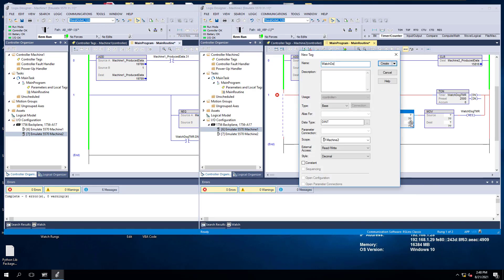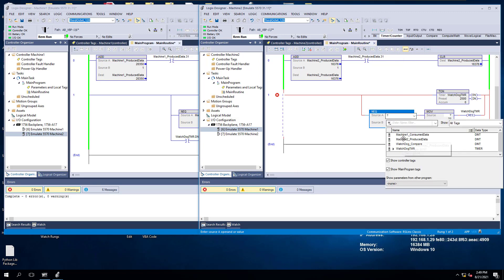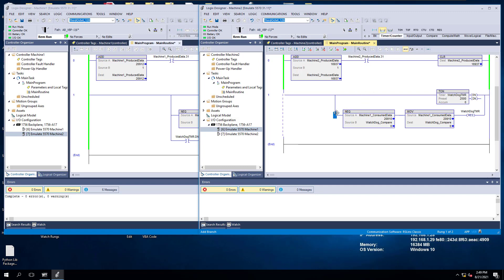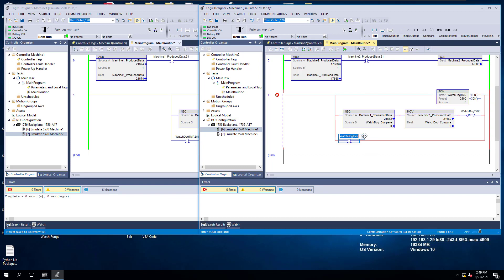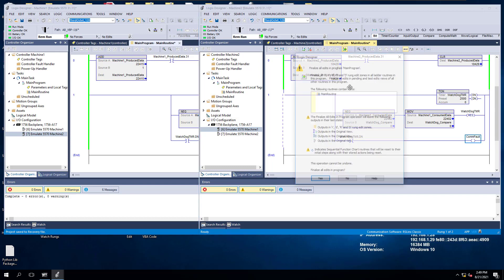We're coming over here and doing the same exact implementation. We'll call that Watchdog Compare — a DINT is a DINT. We're comparing the same data type against the same data type. We want to see the data we're getting from processor one — what's consumed from them. Then we want to basically move it into the compare if it's not equal. If the data is flowing, it's not going to be equal — it's always going to be a good data type, always going to be flowing back and forth. It's not loading anything right now because I haven't finalized the edits. Now we're going to come out here and say if the watchdog happens to go high, then we're going to trigger a fault. This will be a comm fault. Real simple, real easy — making sure the data is flowing.